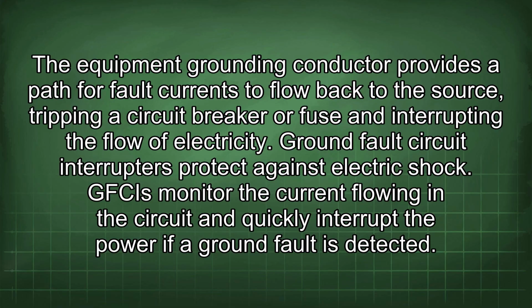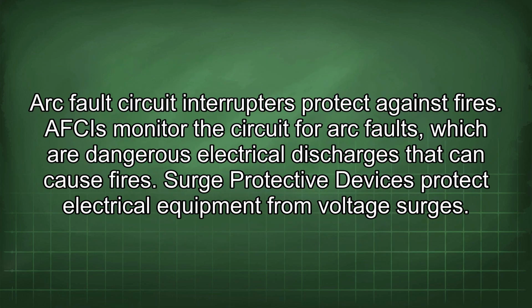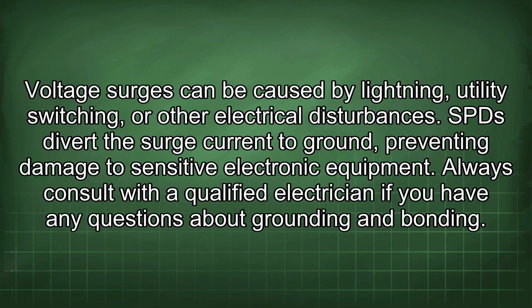Ground fault circuit interrupters protect against electric shock. GFCIs monitor the current flowing in the circuit and quickly interrupt the power if a ground fault is detected. Arc fault circuit interrupters protect against fires. AFCIs monitor the circuit for arc faults, which are dangerous electrical discharges that can cause fires. Surge protective devices protect electrical equipment from voltage surges. Voltage surges can be caused by lightning, utility switching, or other electrical disturbances. SPDs divert the surge current to ground, preventing damage to sensitive electronic equipment.